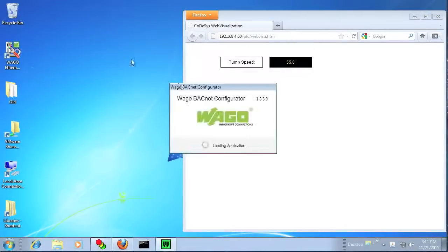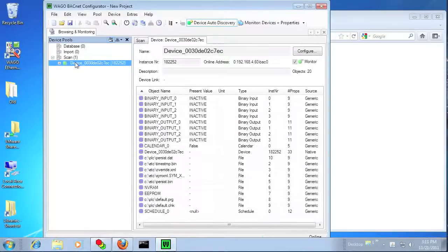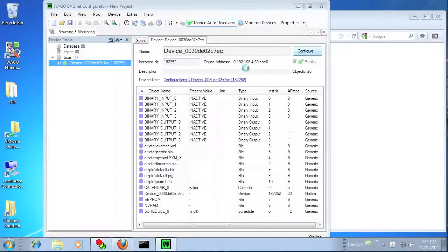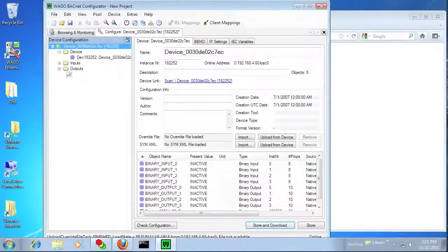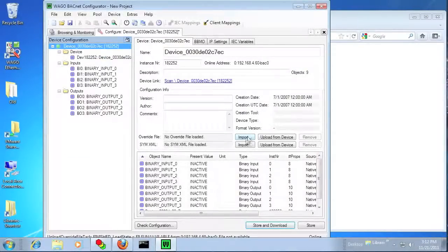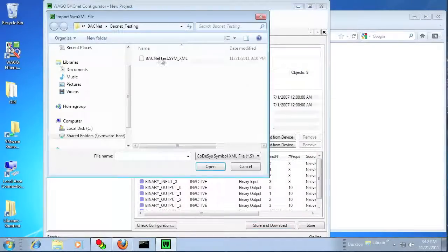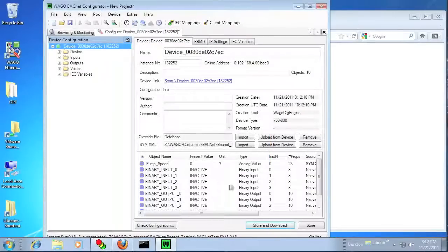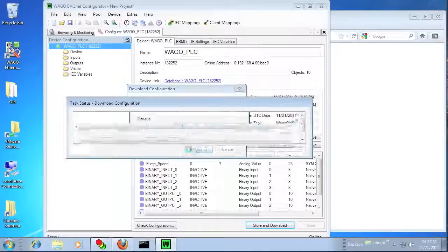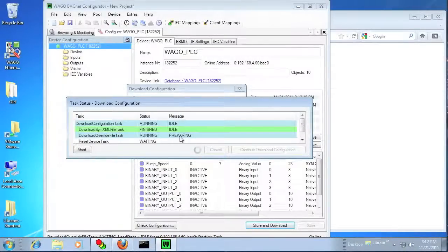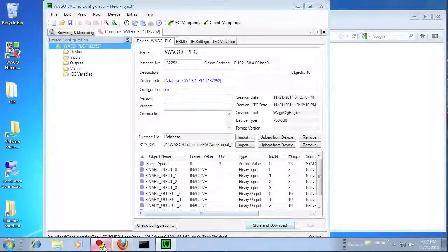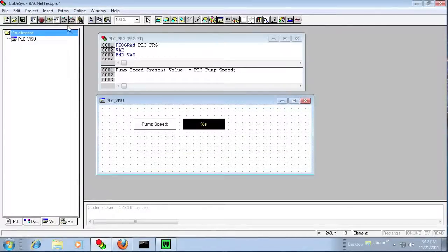I'm going to minimize Codesys now and go into the WAGO BACnet configurator program and hit configure on the device it finds on the network. You can see it says file unavailable for the symbol file. So what we need to do is create that symbol file by importing it from our Codesys project. I'm going to give the device name something more usable — WAGO_PLC. You can see it's uploading the symbol file now, and it uploads that to the file system on the PLC.